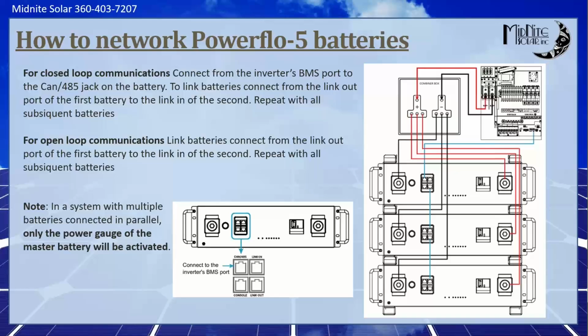Can you have 2 stacks of 4 and wire them in parallel? You sure could. It's a lot based on what you need to pull for charge or discharge current. Say you're doing a single Rosie and a single Classic 150: the Rosie can charge at most 120 amps, the Classic about 100 amps, so the most you could do is 200 amps charge current, and discharge current is about 250 amps on the Rosie. So if you need 8 PowerFlo 5s, could you do 4 in one stack and 4 in another, then bring those two together? You can certainly do that. The wiring really comes down to how you're drawing current and wire size.